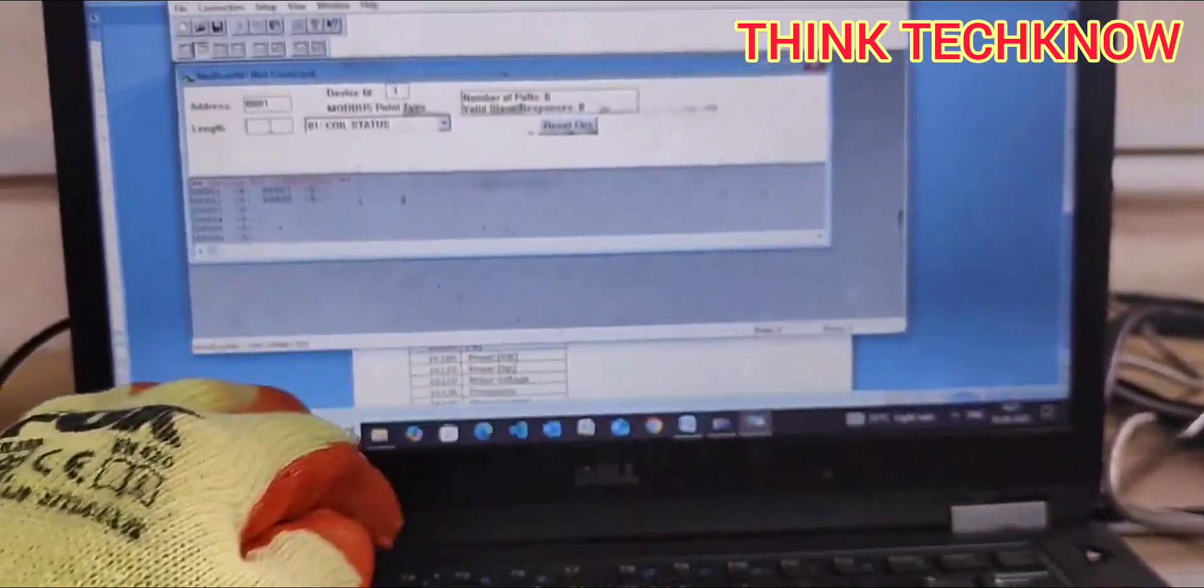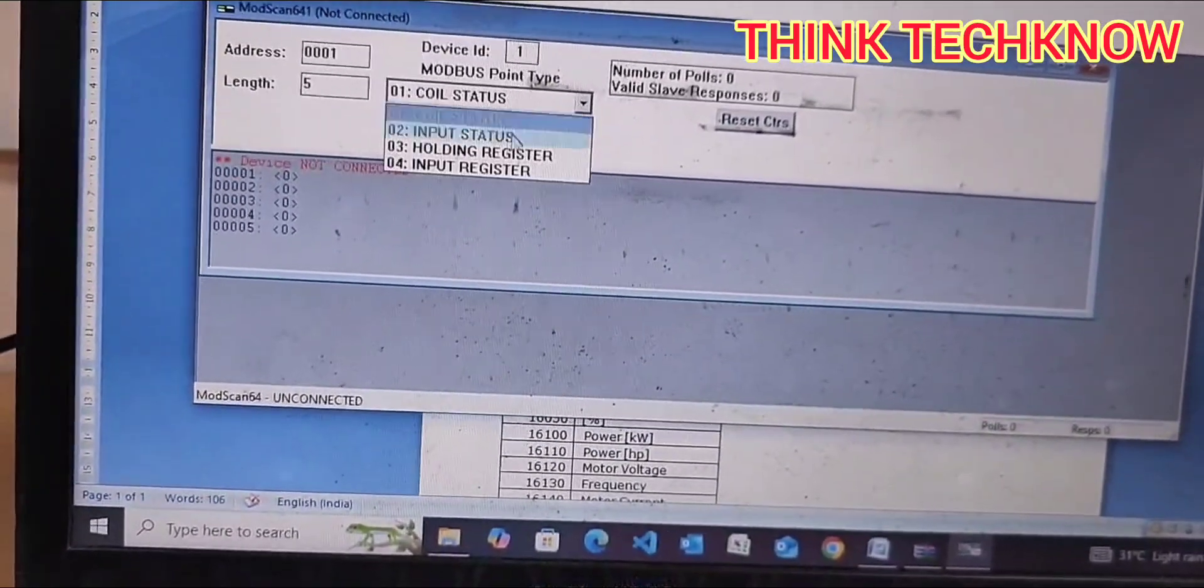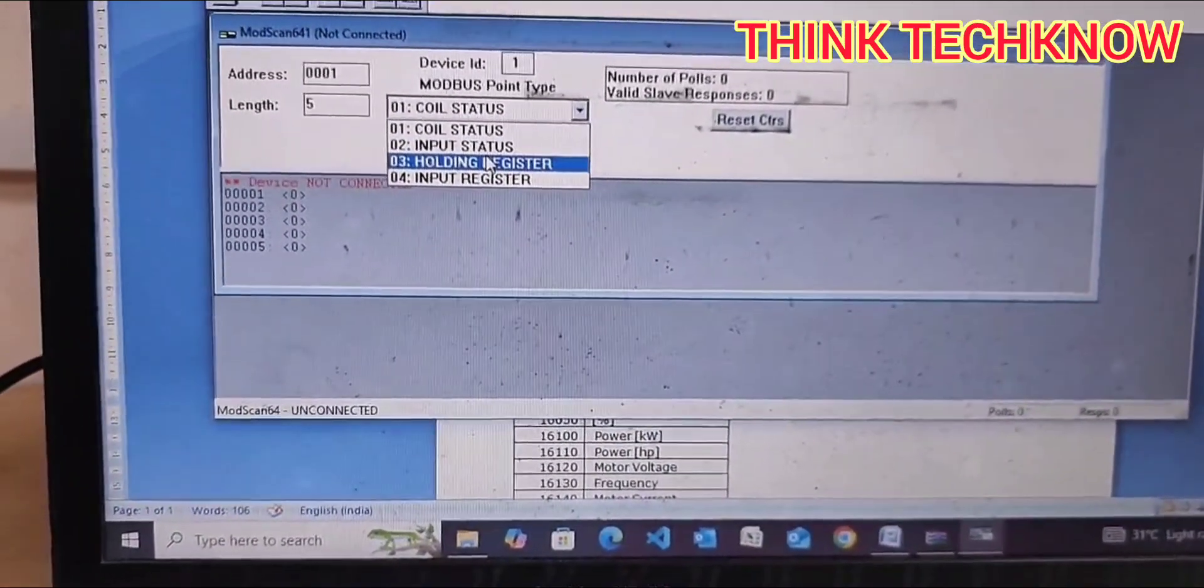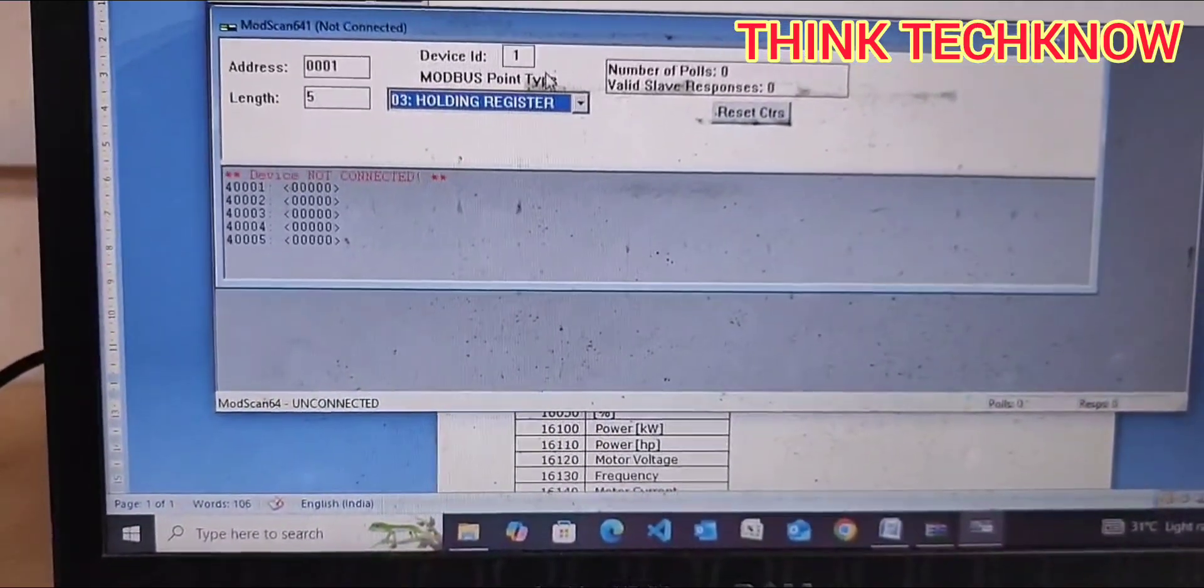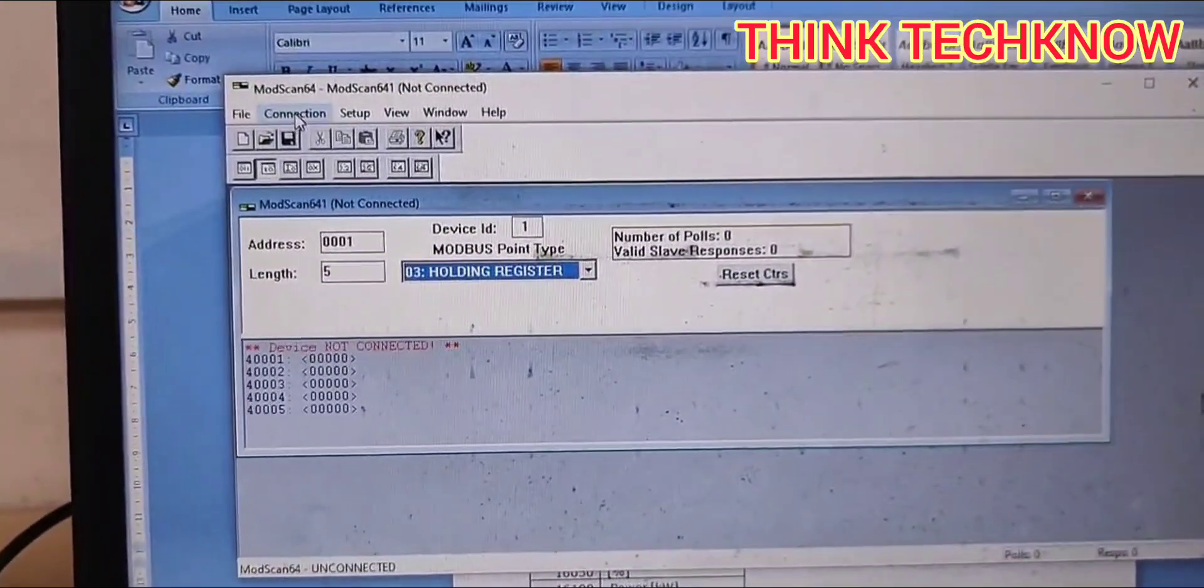You need to connect the VFD. Before connecting, you need to reduce the length to 5 so we can see the clear values on the screen. And you need to select holding register here, and device ID is 1. So I am going to connect it.